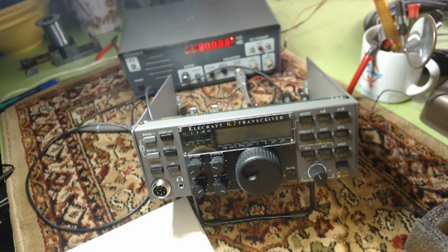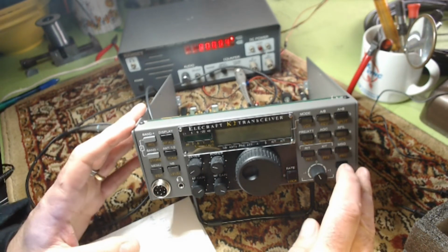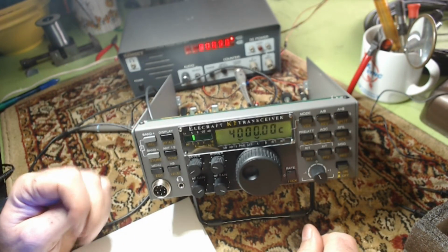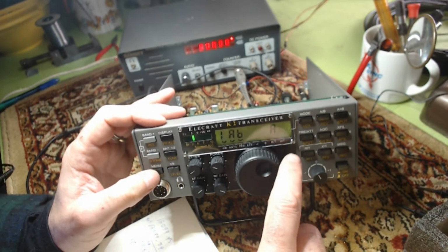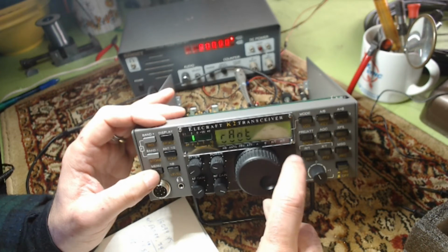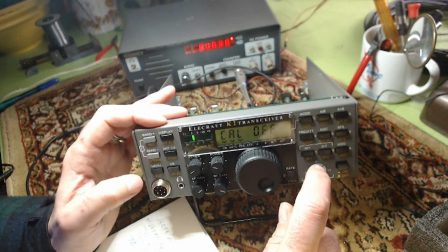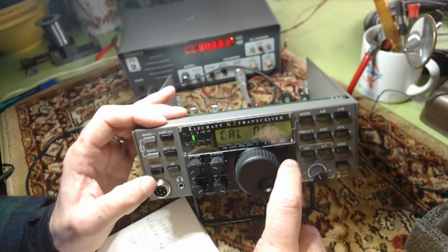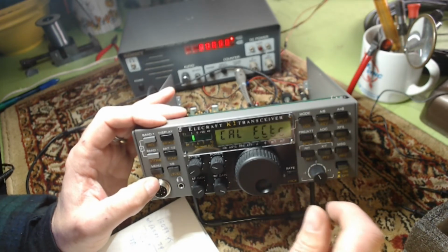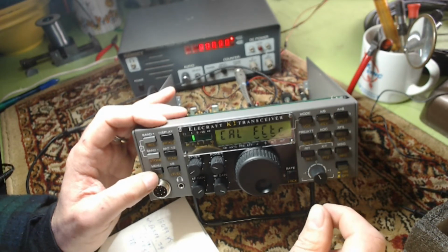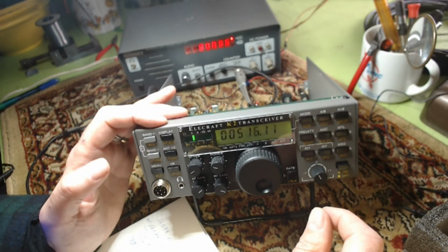All right, I'm back with the setup with the frequency counter. We're backing up a step to the 4 megahertz oscillator calibration and the PLL reference oscillator range test. So we previously had an initial frequency of 12099.37. So we're going to power this up, put on the counter, and see where we are at initially for our first reading. So we go to the menu, we change this to the frequency counter, which is Cal. Whoops, shoot. No, hold it. We turn this to Cal frequency. Yeah, that's right, Cal factor, FCTR. Hold it. Now the frequency counter is on.